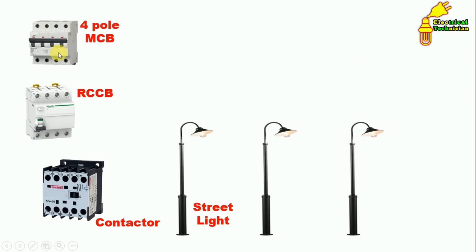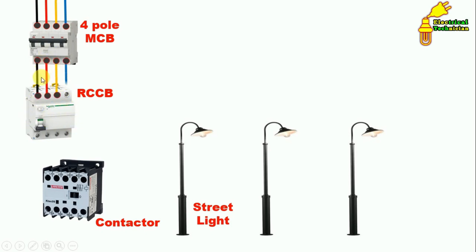For power wiring, first connect power supply to the MCB — neutral supply and three-phase supply. Then to the RCCB also connect neutral supply and three-phase supply. In the contactor, there are three terminals L1, L2, L3, and on these three terminals we connect power supply.